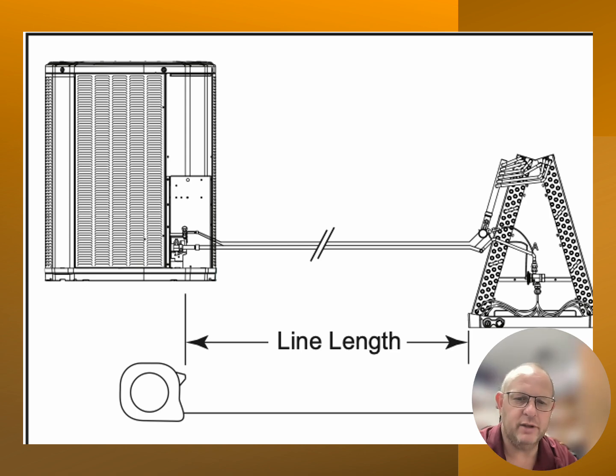We have certain variances, like we can't go vertically too far high, or we can't go horizontally too far, or we can't go vertically down too far, or we're going to end up messing with the capacities that these systems can produce, ending up getting flash gas inside of our liquid line and a lot more other things that could go wrong, because the manufacturer said, hey, you can't go over a certain length. Otherwise, the system's not going to operate like we're telling you it's going to operate. So line length from the outdoor unit to the indoor unit.